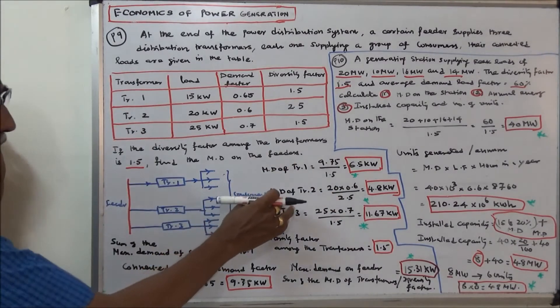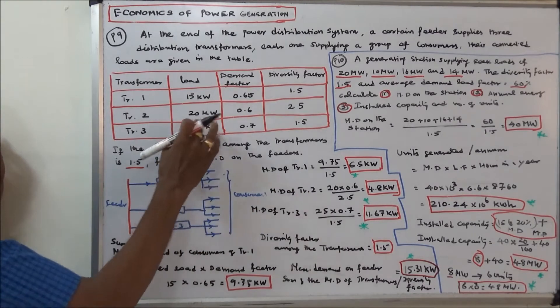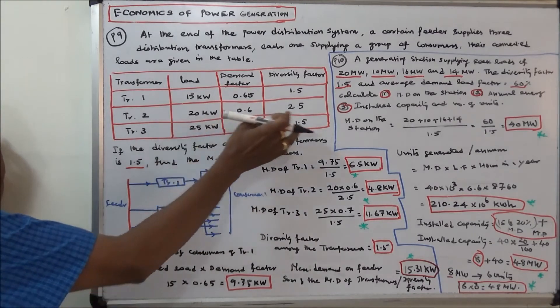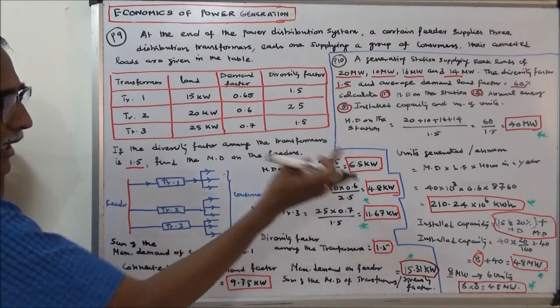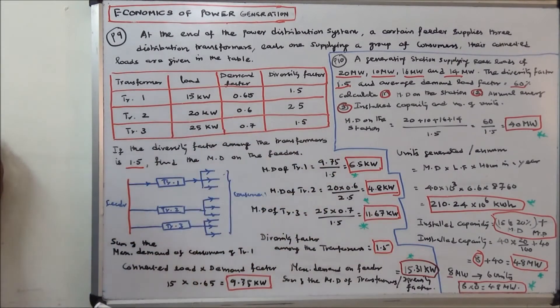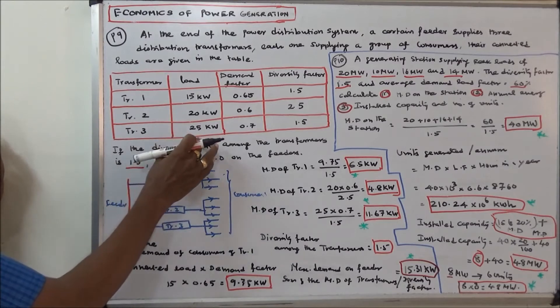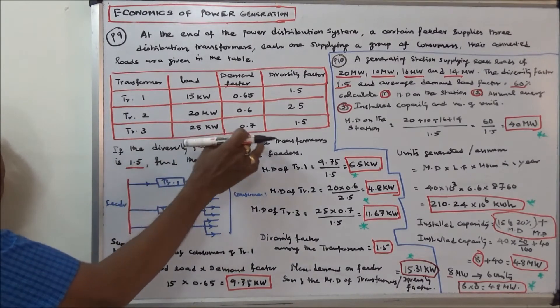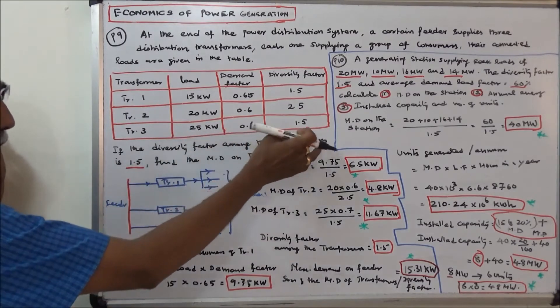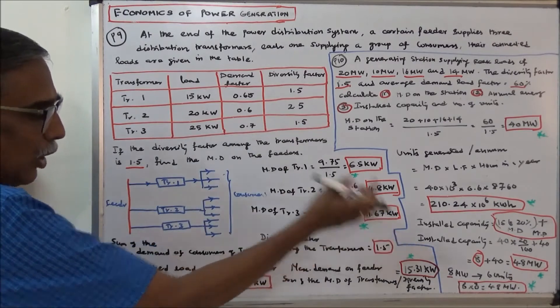Similarly, the maximum demand of transformer two is equal to 20 multiplied by 0.6 divided by 2.5, which equals 4.8 kilowatts. The maximum demand of transformer three is equal to 25 multiplied by 0.7 divided by 1.5, which equals 11.67 kilowatts.